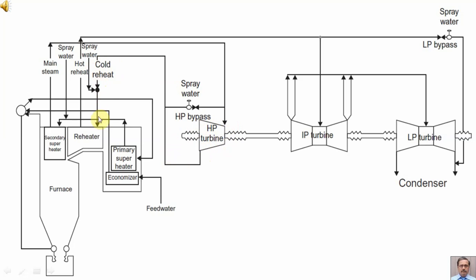The cold reheat goes back to the reheater section of the boiler. Before entering the reheater, the cold reheat is sprayed with water to control the temperature of the hot reheat, making it comparable with the main steam temperature. The steam entering the reheater is cold reheat, and the steam coming out of the reheater section is hot reheat.